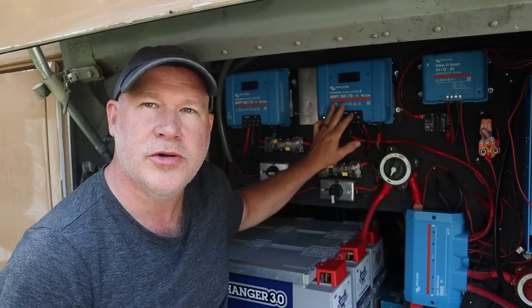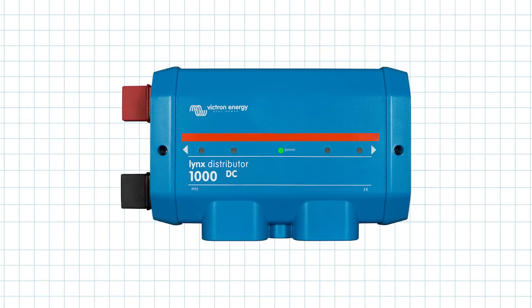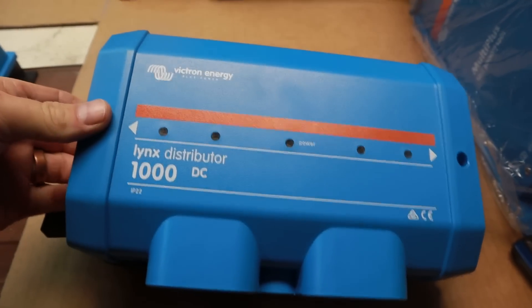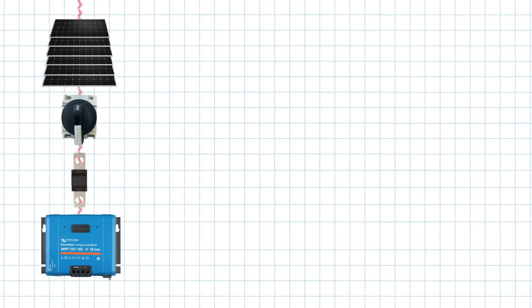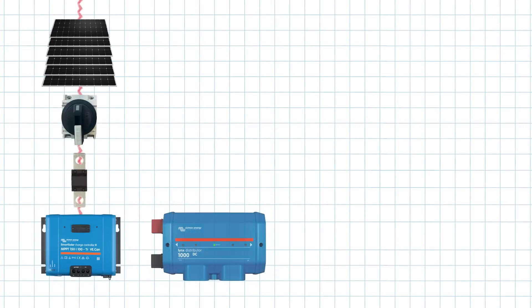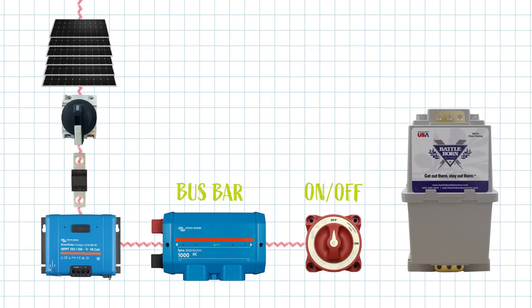Continuing on from the solar charge controller, that energy goes on to our Lynx Distributor 1000 DC, which for us is acting as a fused bus bar. A bus bar acts as a junction box letting us connect multiple components to it to both charge and distribute power to our system. Following the power from our solar panels through our MPPT controller and through our Lynx Distributor, we head over to our batteries via an on/off switch. Having an on/off switch between our batteries and our Lynx Distributor allows us to cut all power off from our batteries to the entire system.